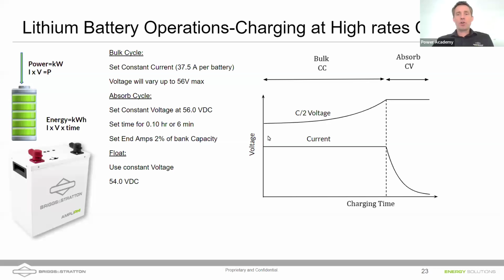So this is what that charge cycle looks like at a C over 2 rate. You're charging, voltage comes up, you hit 56, you maintain it at 56 for 6 minutes, and your charge cycle is complete. This is called the bulk part of the cycle, the constant current section. The absorb part is when you're at a constant voltage, with decreasing current as that battery fills up.